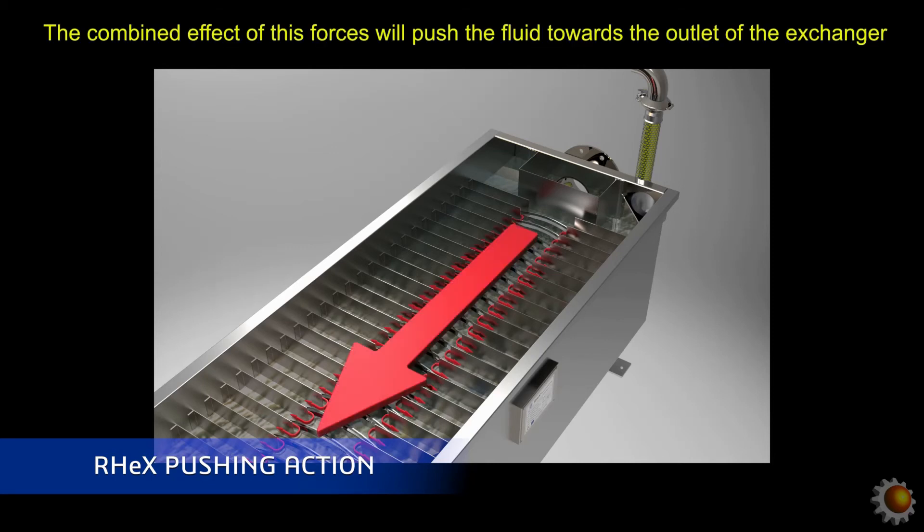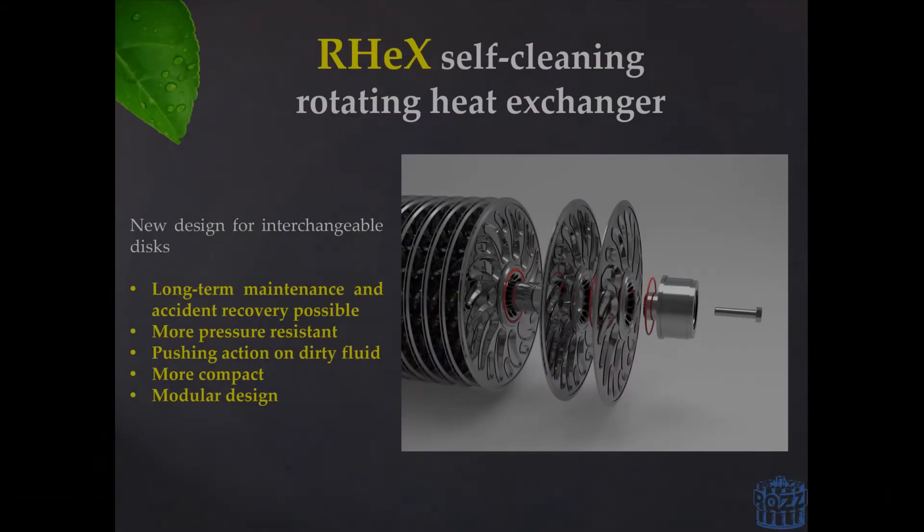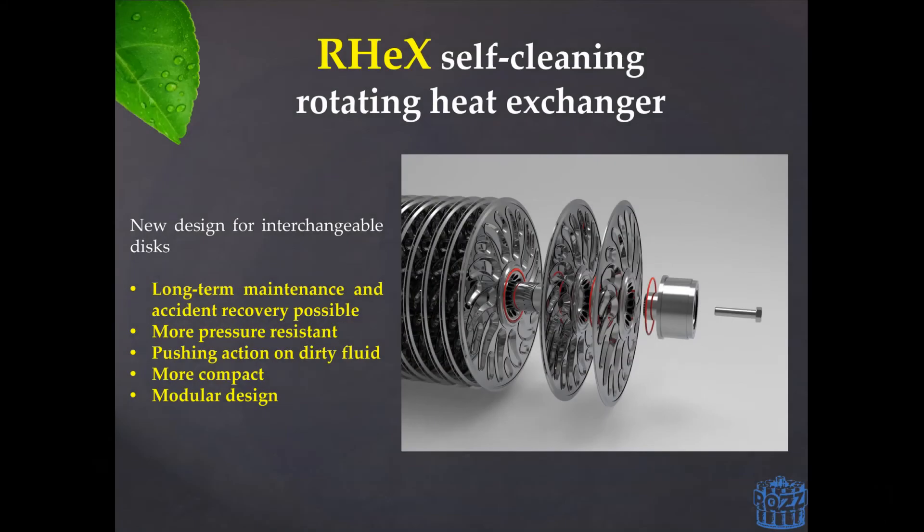This pushing action becomes very useful when dealing with particularly viscous and dense fluids. Another important upgrade is the way in which the rotors are made. On RCR units, the discs used to be welded between each other. Now the discs are placed with a gasket between them, pressed together and kept in position by a locking end cap. This not only allows for easy replacement of a single disc in case of an accident, but it also allows us to build a more compact unit. Since welding is not required, the discs can be placed closer to each other, making RHeX a more compact and more efficient unit.